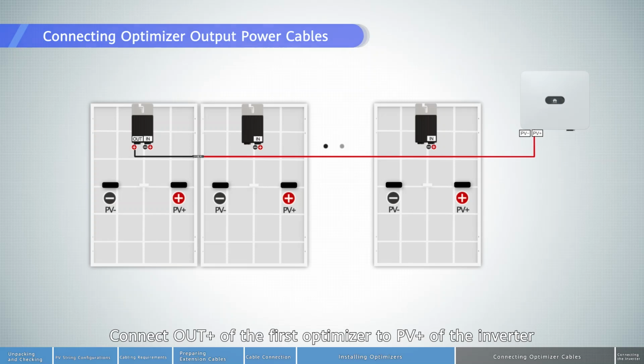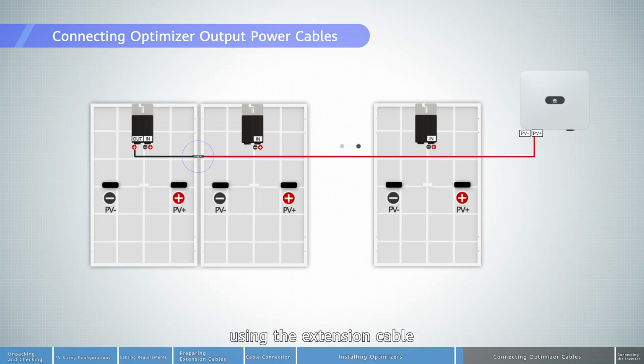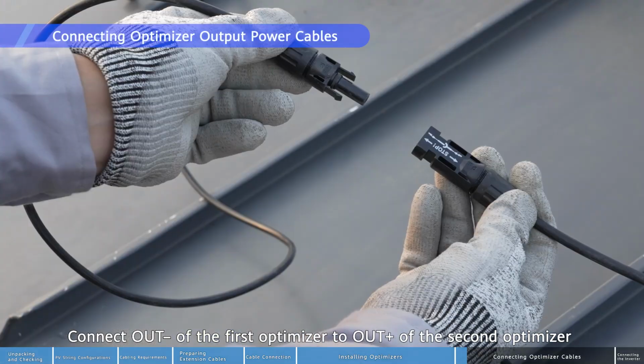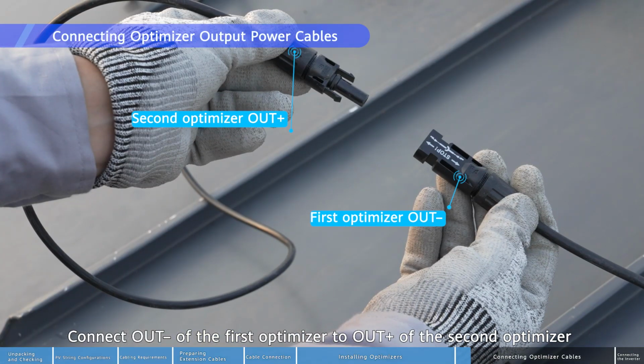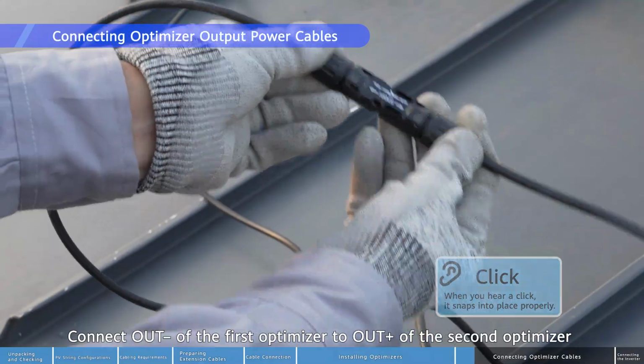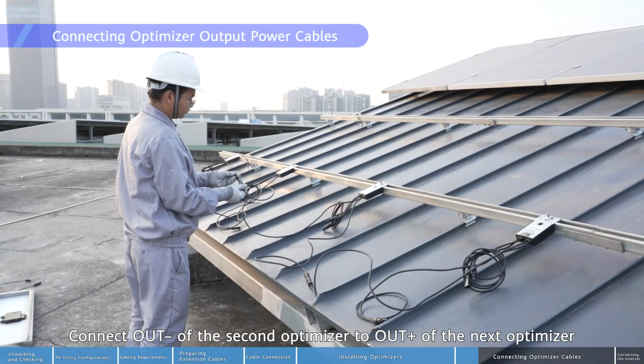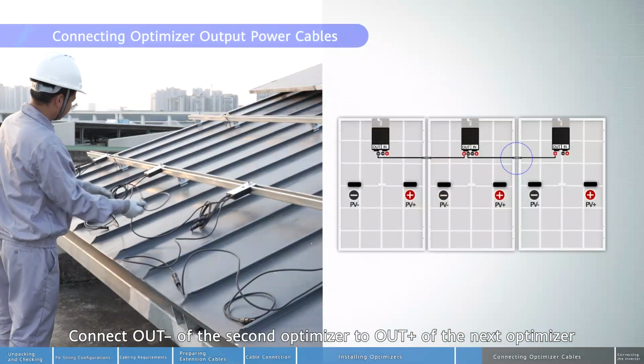Connect out positive of the first optimizer to PV positive of the inverter using the extension cable. Connect out negative of the first optimizer to out positive of the second optimizer. Connect out negative of the second optimizer to out positive of the next optimizer.